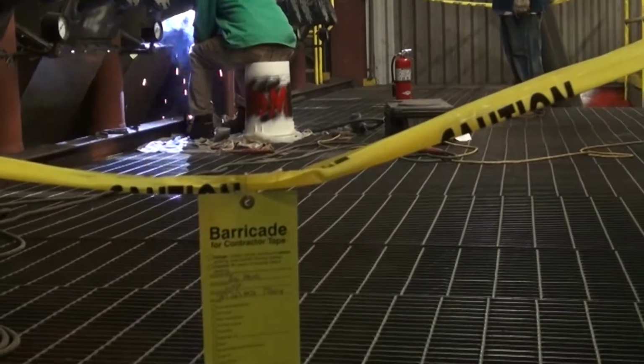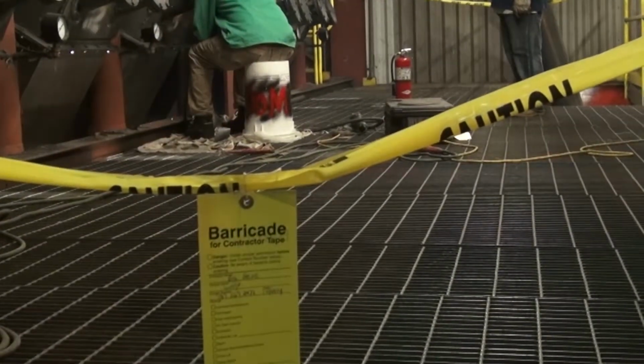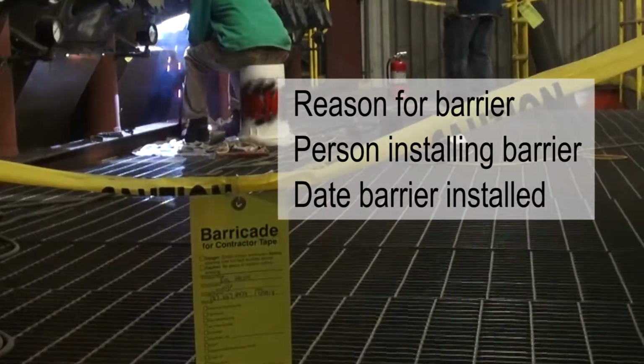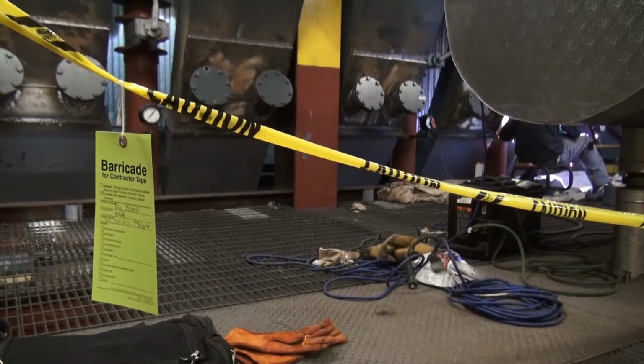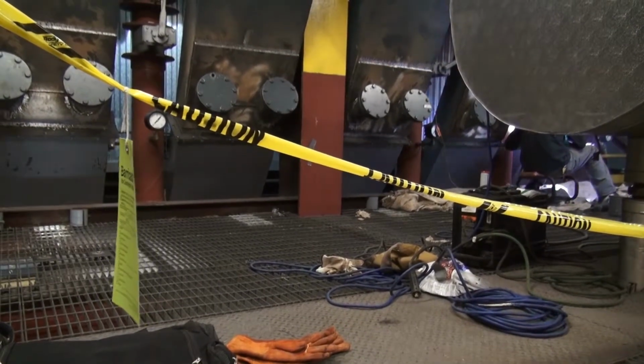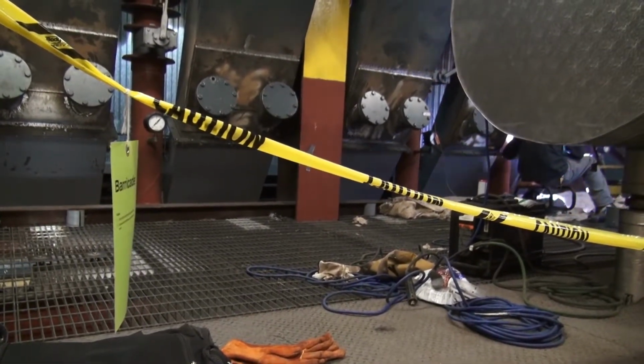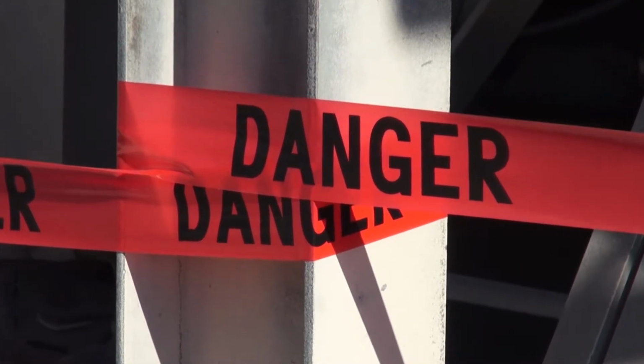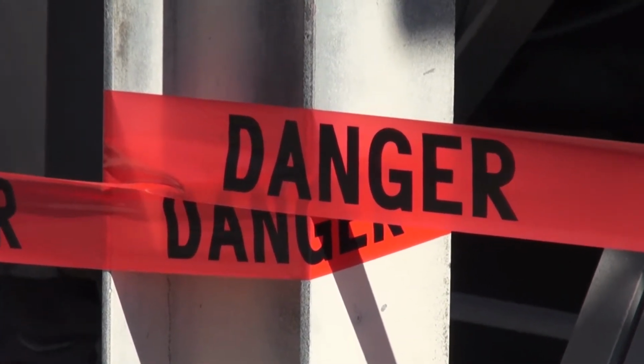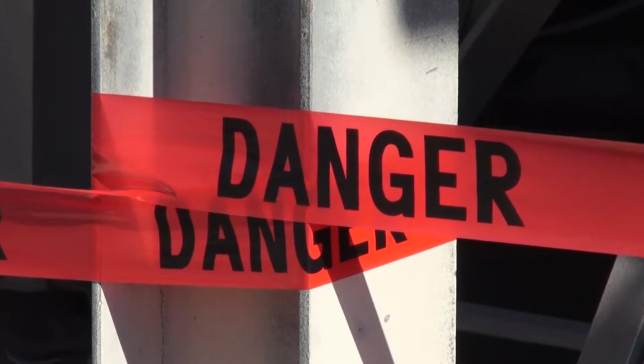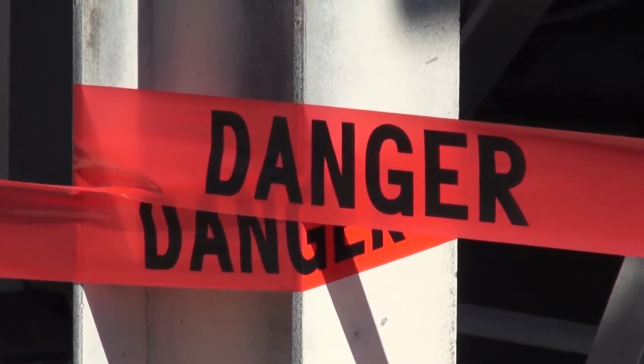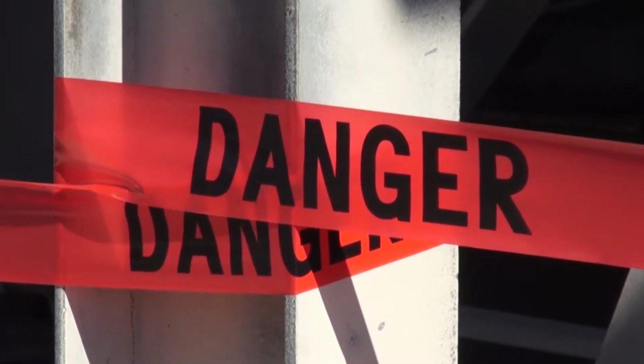All barricades are to have a tag affixed containing the following information: reason for barrier, person installing the barrier, and date of barrier installation. A barrier with yellow caution tape may be entered after determining that conditions for safe entry exist. A barrier with red danger tape may not be entered unless the person is directly involved with the hazard or permission has been obtained from the person in charge and after verifying proper safety precautions have been taken.